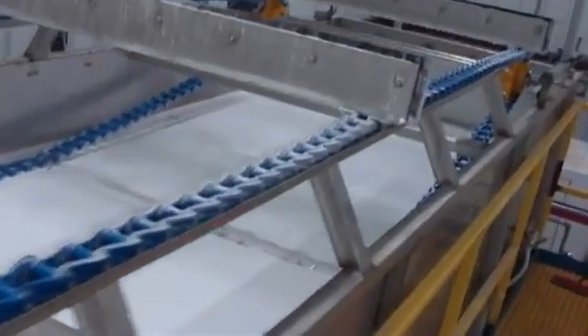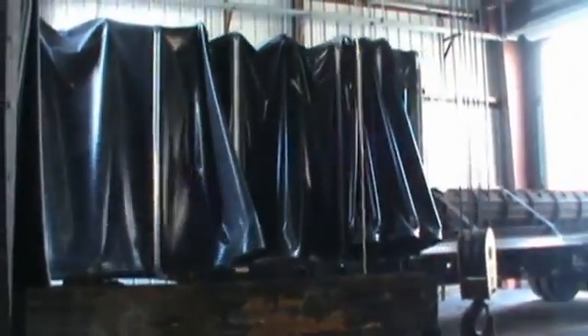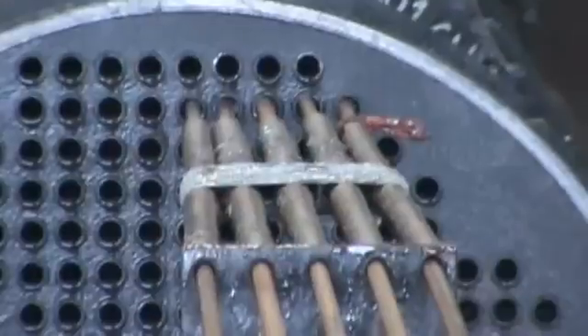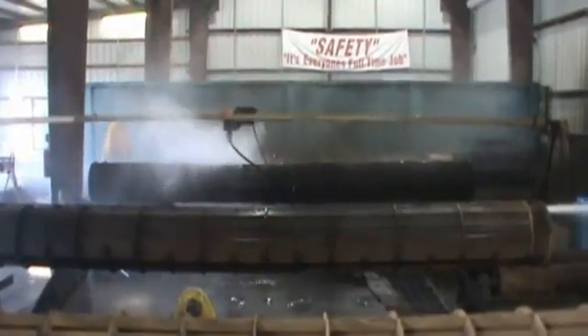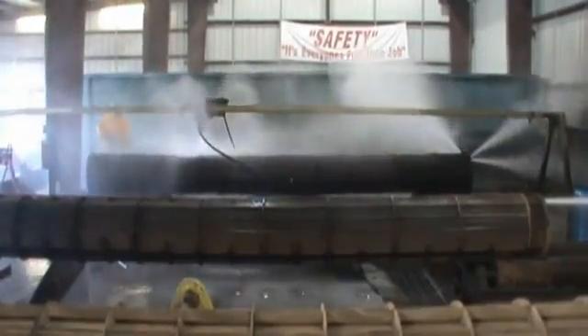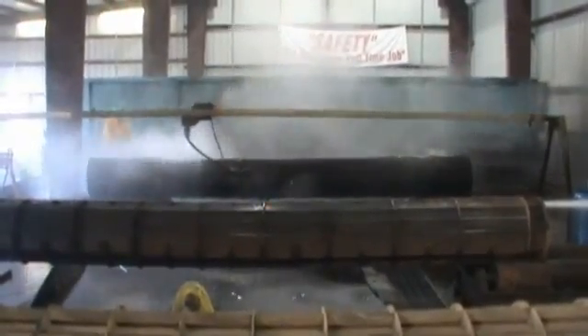The advantage of picking up and transporting two large exchanger bundles at a time to the Channelview facility and using the multi-tube lancing cleaning system is turnaround time. While the on-site crews were blasting four heat exchangers, the off-site crews at the Channelview facility were also blasting and cleaning four exchangers.